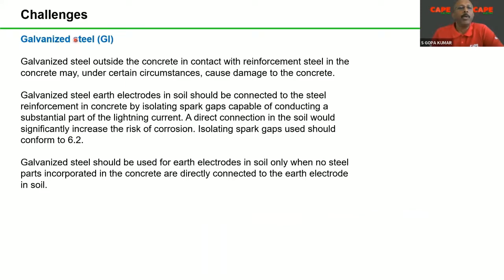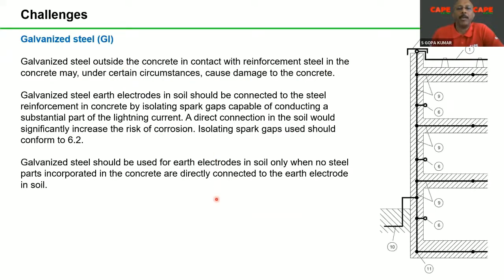is a problem. Now, further, these are the further classes. For example, galvanized steel outside the concrete in contact with reinforcement steel may under circumstance cause damage to concrete. What does it mean? You have the building here. Now, item number 10, we are taking a connection outside from the concrete to do something in soil. And if you are using galvanized steel in this soil, it will be forced for accelerated corrosion. Galvanized steel will disappear within few years, within few months. So galvanized steel electrodes in soil should be connected to the steel reinforcement in concrete by isolating spark gap. That means here a direct connection in the soil would significantly increase the risk of corrosion. Isolating spark gap should be used.